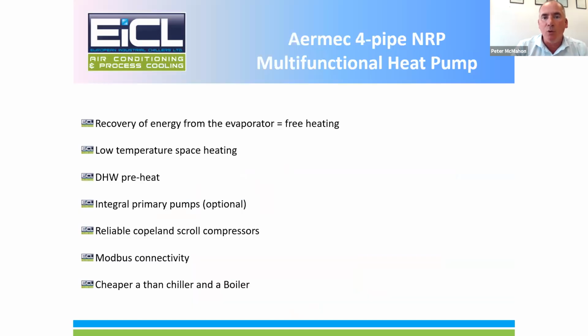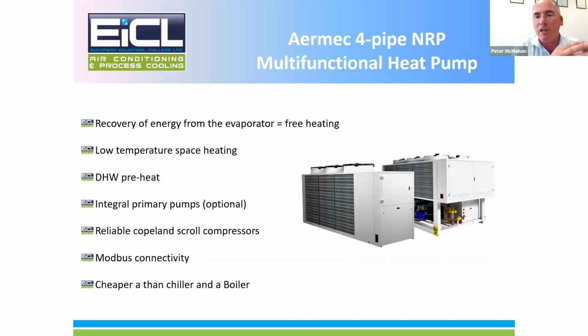So what I want to do is to explain firstly what a multifunctional heat pump is. And a lot of you guys will know what they are insofar as you know all the components that are in them. Just as you have a chiller, you have a compressor, a condenser, an expansion valve, and an evaporator. The difference with a multifunctional heat pump is you have more intelligent controls and you have a multiple of four-way valves and suction accumulators to stop liquid refrigerant coming back to your compressors, which is very important.